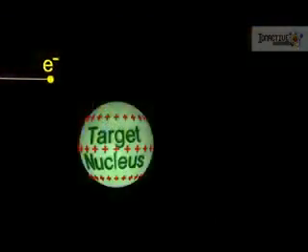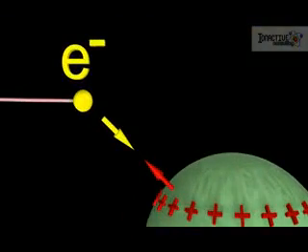The target is typically a piece of tungsten or molybdenum, which may be embedded in a stationary water or oil-cooled rod, or on a rotating disc. The high-speed electrons collide with the target and rapidly lose energy. There are two X-ray producing interactions between the incident electrons and the atoms in the target. In the first, electrons are scattered by electrostatic interaction with the nuclei of the target material.